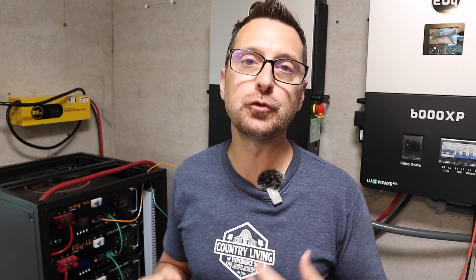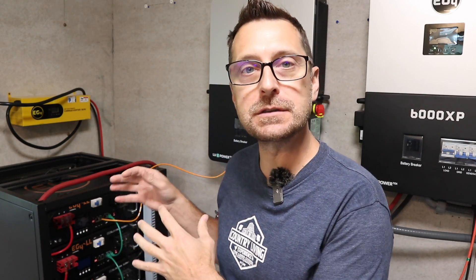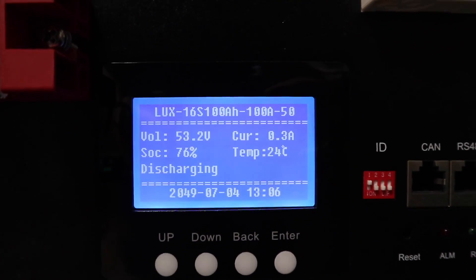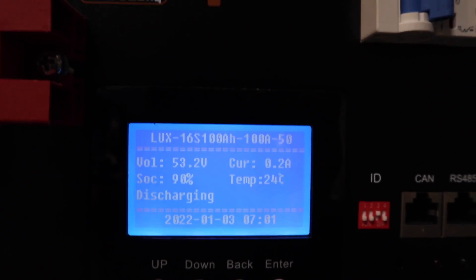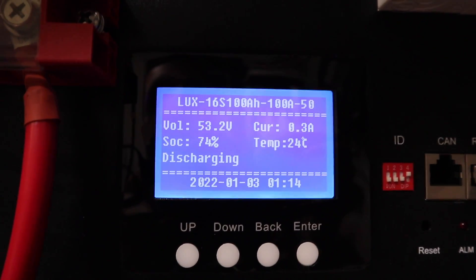This thing that I have named voltage drift from state of charge is happening with some of my batteries. Some of the batteries have a state of charge telling me 90%, some are as low as 72%. However, if you look at the voltage on each battery, they are all the same at 53.2 volts. This is our fourth battery down in the stack — 53.2 volts at 76%. Another one: 53.2, 72%. Another: 90% state of charge, still 53.2 volts. And another: 74%, 53.2 volts.